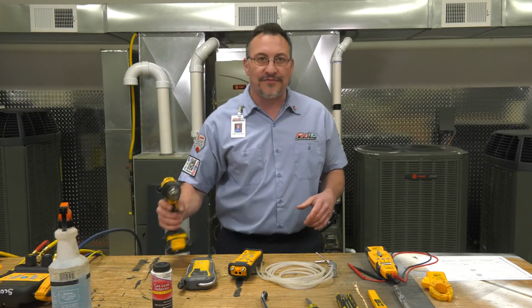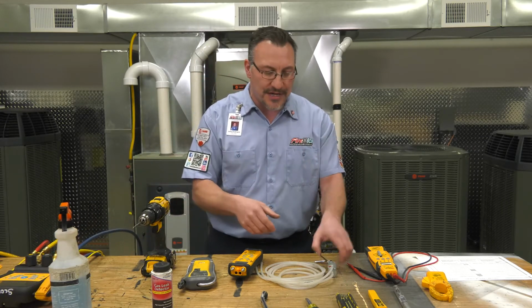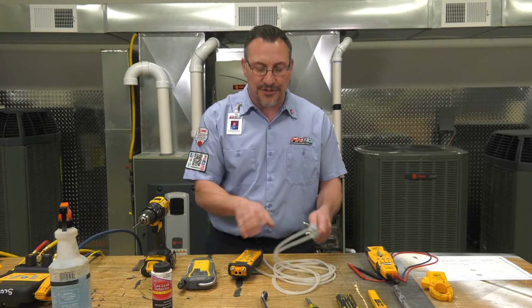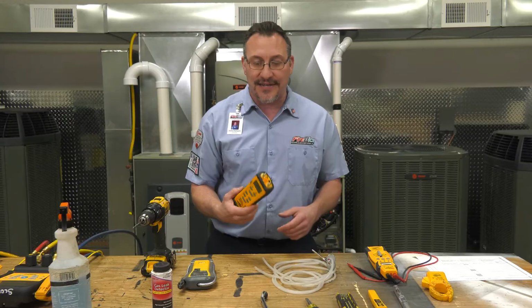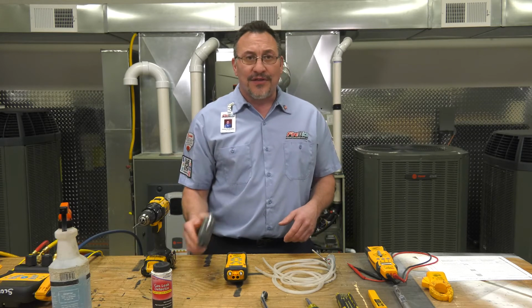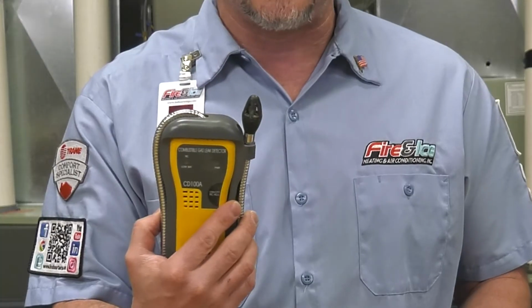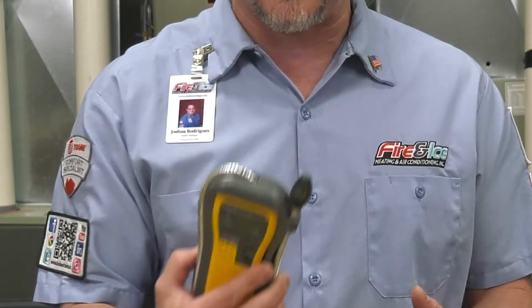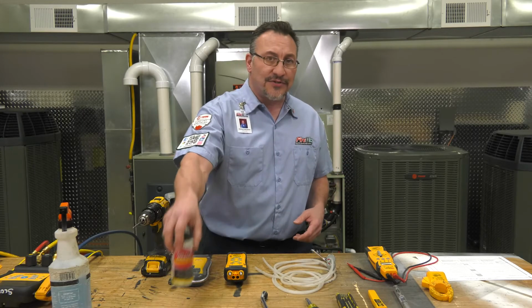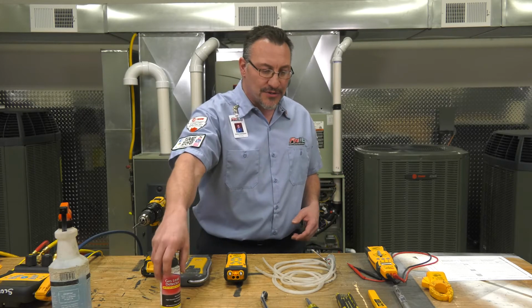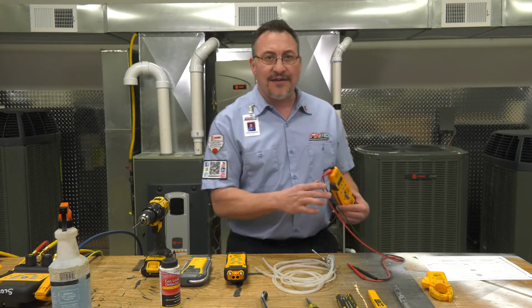Obviously you need some sort of drill - we have to drill holes in a couple things to take readings. We've got static pressure ports, a dual port manometer that reads static pressure and gas pressure. For safety, we want to make sure we don't have any gas leaks, so here's a digital leak detector, or we can do some old school soap bubbles - those work great. You also have a multimeter.